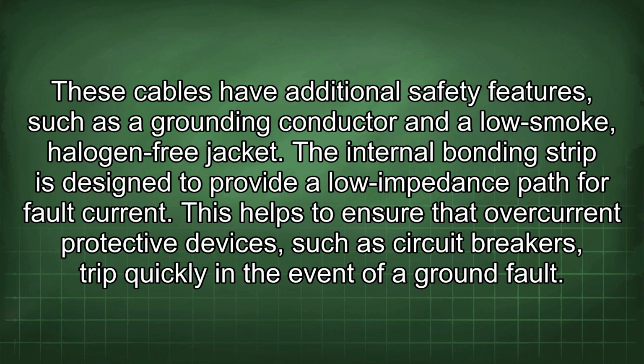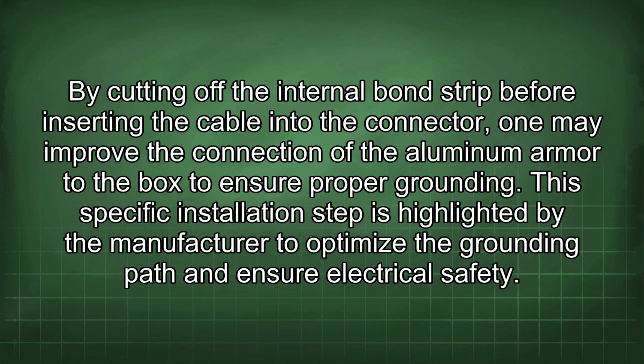This helps to ensure that overcurrent protective devices such as circuit breakers trip quickly in the event of a ground fault. By cutting off the internal bond strip before inserting the cable into the connector, one may improve the connection of the aluminum armor to the box to ensure proper grounding. This specific installation step is highlighted by the manufacturer to optimize the grounding path and ensure electrical safety.